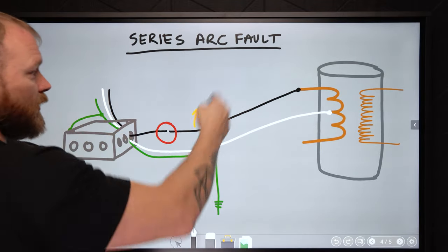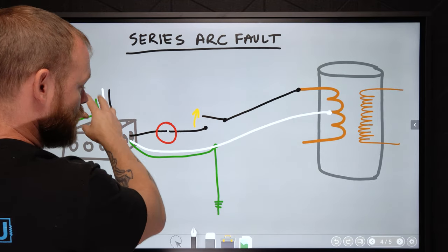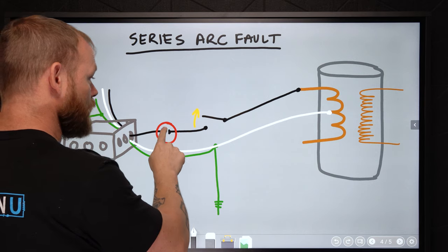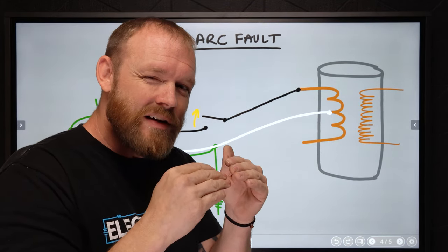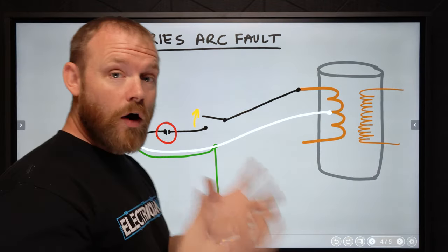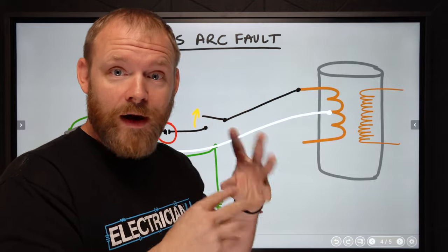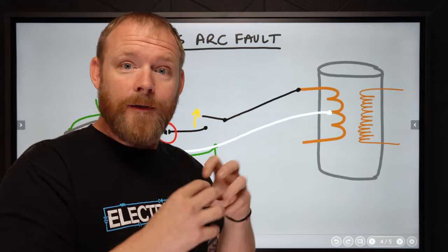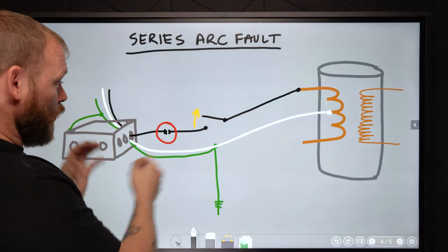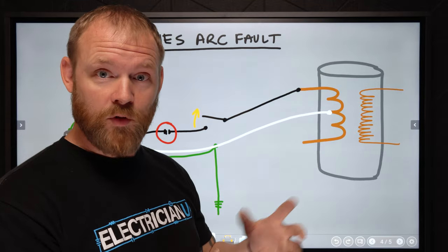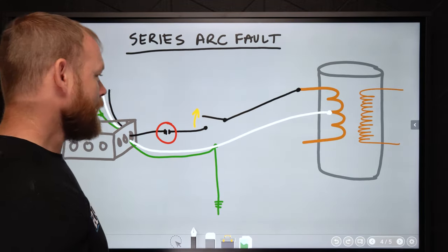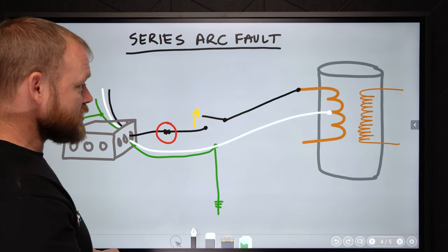In a series arc fault, the fault is in a conductor in series — like two screws with a loose termination that aren't quite touching but arc across the gap. Arc fault breakers have a small board with logic that recognizes the signature of a series arc and trips the breaker. The breaker part still works normally for thermal and magnetic trips, but it also has the added capability to detect what series arc characteristics look like and open the circuit when those occur.